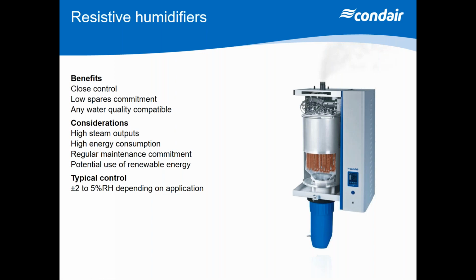And it will modulate from 0 to 100% of its output because I can change the rate of that pulsing via those solid state relays. So it will give me much tighter control. Even though I'm still doing a dilution cycle drain, I'm controlling that water level, so I don't come off the boiling point as much. But by modulating the energy that goes to those heating elements, it's going to give me that plus or minus 5% control. Now, if I want finer than that, I can actually use RO water with these units. Because I'm not relying on conductivity, if I'm in a hard water area, I can feed RO and reduce the maintenance requirements. And that will give me between 1 and 2% RH control because I'm not having to do any dilution cycles.